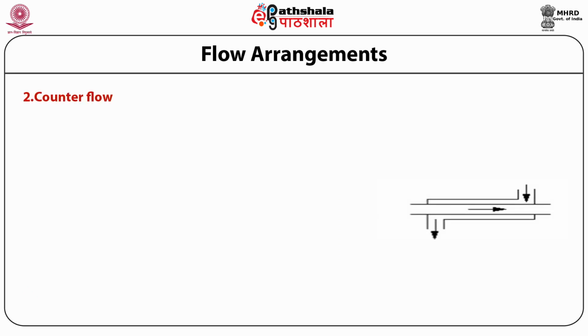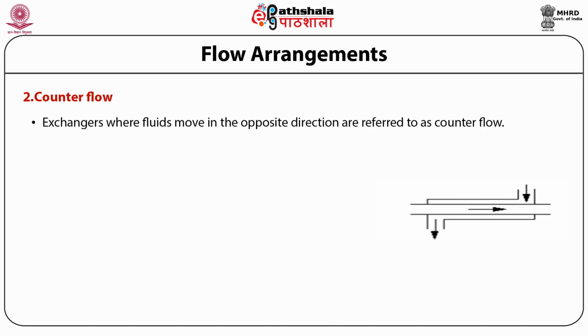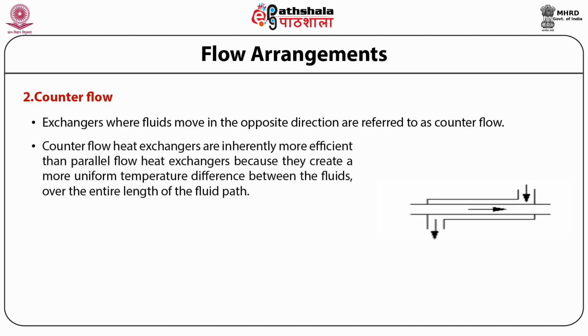The next flow pattern is counter flow. As shown in the diagram, in the case of counter flow, the hot fluid moves opposite to the direction of the cold fluid. Exchangers where fluids move in opposite directions are referred to as counter flow. Counter flow heat exchangers are inherently more efficient than parallel flow heat exchangers because they create a more uniform temperature difference between the fluids over the entire length of the fluid path.